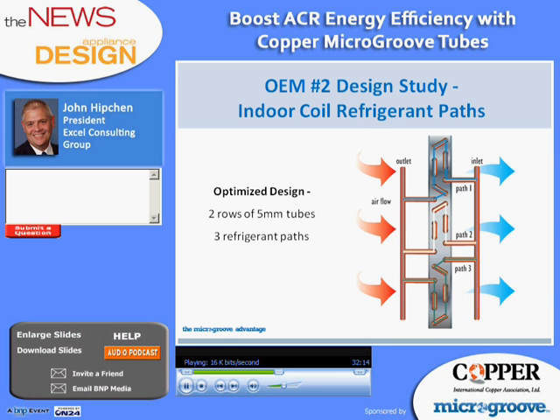Looking at the optimized design here, we see 3 distinct refrigerant paths, again allowing an acceptable pressure drop with the smaller diameter 5mm tubes. Note the inlet and outlet are now reversed from the original design, resulting in refrigerant flow in the opposite direction of the air.